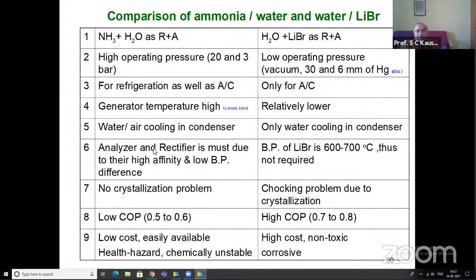Now here we need an analyzer and rectifier to separate the water vapors from the ammonia vapors because of the high affinity between the water vapor and ammonia vapor and the low boiling point difference. In case of water lithium bromide, this requirement of rectification is not needed because the boiling point temperature difference is also very large. In case of ammonia water, there is no problem of crystallization.